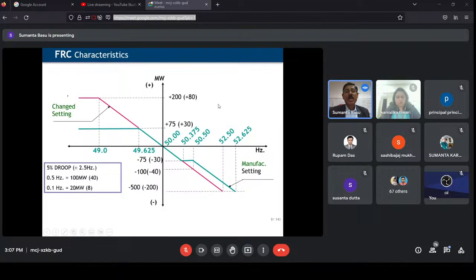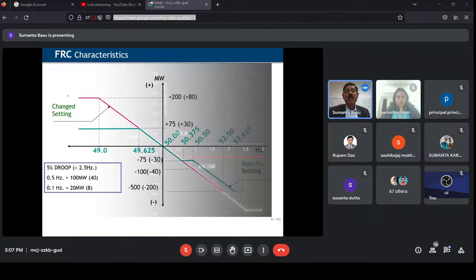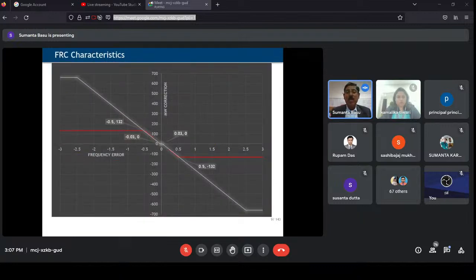Now, based on experience, this also gets modified. So it is modified to accommodate the disturbance because of the ripple. So it is plus minus 0.03 hertz. So our power system frequency band is 49.95 to 50.05. To accommodate any variations of load, if the frequency varies like this, a plus minus 0.03 hertz dead band has been given to eliminate those ripple factors. So this is, at present, the frequency response characteristics being followed by the power system network operating in India.